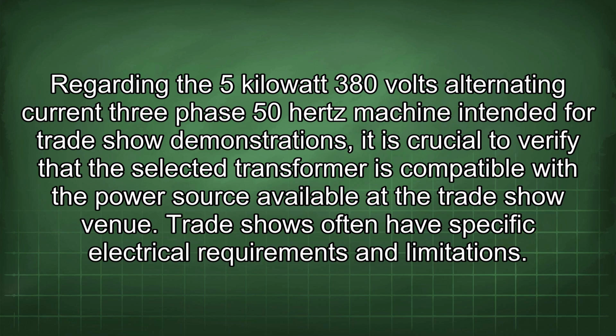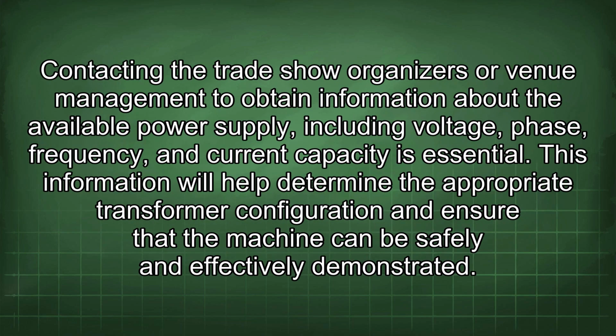Regarding the 5 kW 380 volts alternating current 3-phase 50 Hz machine intended for trade show demonstrations, it is crucial to verify that the selected transformer is compatible with the power source available at the trade show venue. Trade shows often have specific electrical requirements and limitations. Contacting the trade show organizers or venue management to obtain information about the available power supply, including voltage, phase, frequency, and current capacity, is essential. This information will help determine the appropriate transformer configuration and ensure that the machine can be safely and effectively demonstrated.